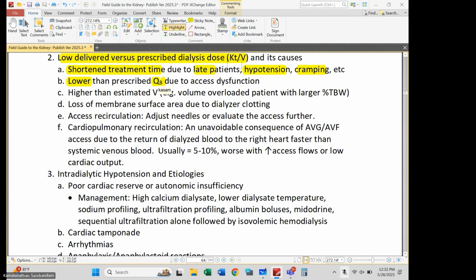So blood flow is the one that you need to certainly think about as well. First, again, we don't typically have problems with dialysate flow rates or dialyzers. Blood flow rate can certainly go down because I'm having catheter problems or access problems or my needles are in against the wall. So remember, blood flow rates, look to that. What is your bedside assessment that the access is working well? Remember, you want an access pressure that's less than half of your blood flow rate.